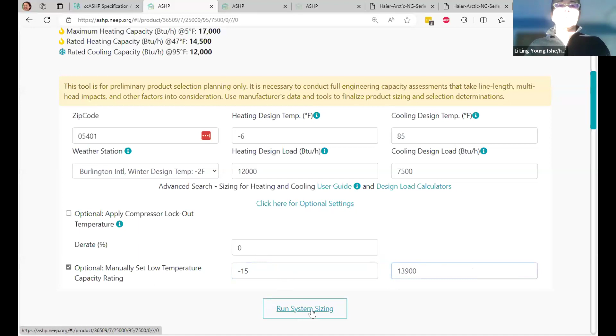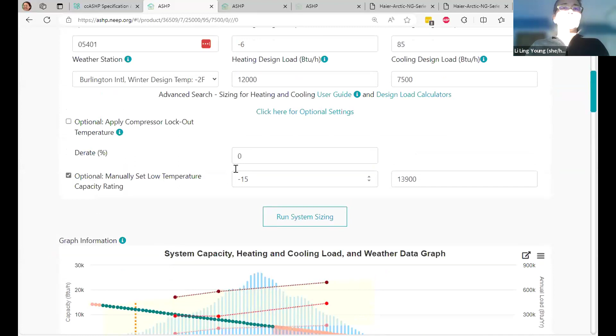Okay, now let's look at what this smaller heat pump looks like—maybe this will be better. So, just so I don't forget again: if I didn't put in this extra information about performance at minus 15 degrees, this yellow wedge would just end at 5 degrees. But because I put in that extra info, the yellow extends all the way out to minus 15, giving us the information we need right at the design conditions.